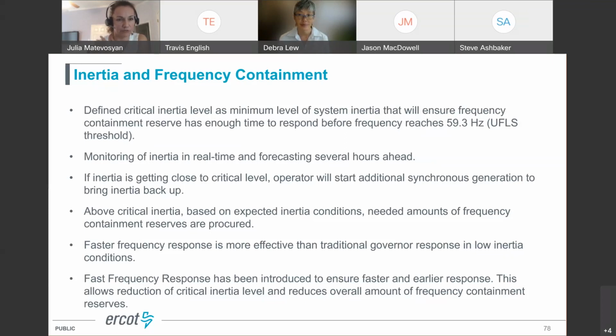We monitor inertia in real time. If inertia is close to critical level, system operators have processes in place to start additional synchronous generation right away. So that's the workaround that we have, but we never actually got to that critical level of inertia. So that's just a precaution for now. And above critical inertia, we base the requirement for frequency containment reserves on inertia conditions. So we need less reserve when inertia is high and more reserve when inertia is low.